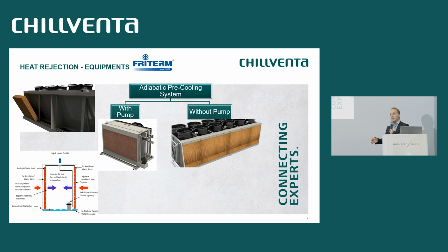Some customers want to take this water, filter it and reuse it. For that, we make a with pump system. We can use wastewater thanks to the pump, but there are some problems here, because when you make too much recycling, the water gets harder and harder, so it will reduce your pad's lifetime. So for that, we have a bleed off system option, so it will renew your bottom tray's water, so it will increase your pad's lifetime.